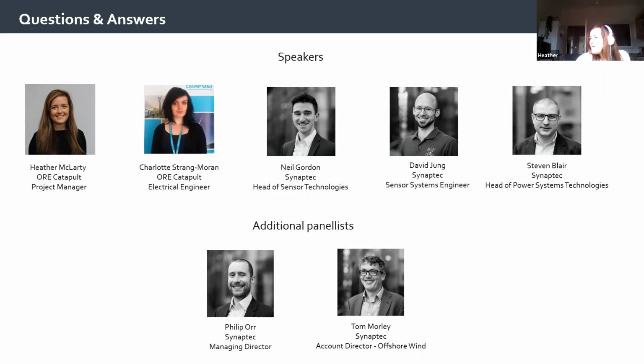Would the installation downtime be envisioned to be 1 day or multiple days? So I think the answer is that in this particular installation, we covered 2 installation locations, one in the turbine, one in the onshore side, and the interrogator, and that took a day. So certainly it's going to take longer than a day to instrument a whole string or more of an array, but even then it's going to be significantly quicker than pretty much any other instrumentation technology that's giving the same result, because we don't require, again, all that supporting infrastructure to be there.